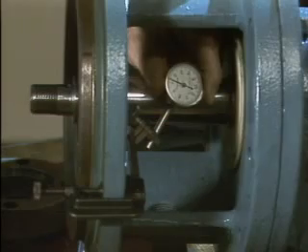There are other important checks that should be made before a mechanical seal is installed. Some of these checks involve the use of dial indicators. One important check is testing for shaft runout. A shaft that's bent or out of round can damage pump components and prevent a mechanical seal from operating properly.